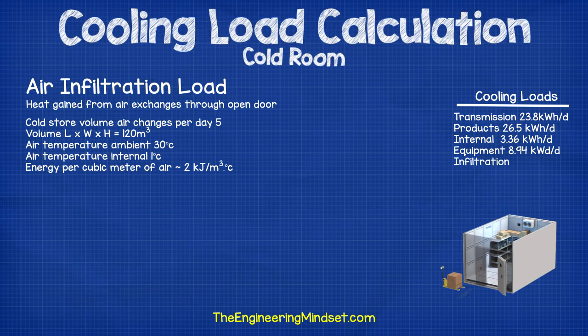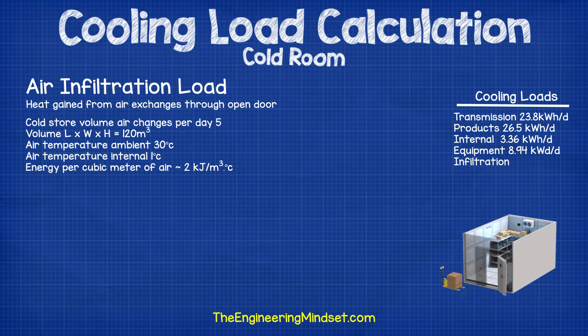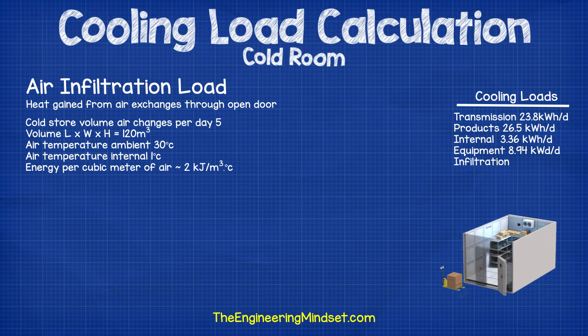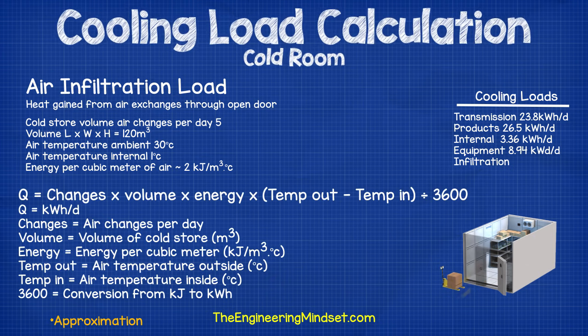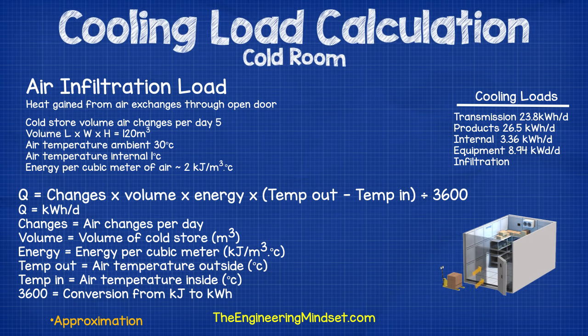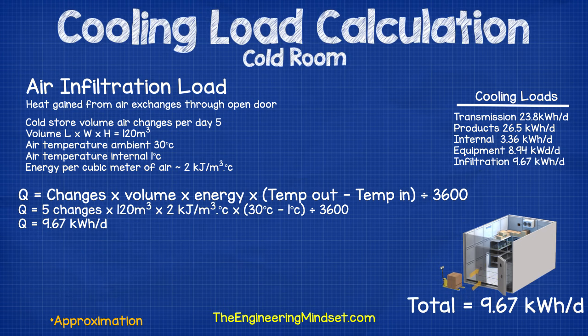Now we need to calculate the heat load from air infiltration. I'm using a simplified equation, but depending on how critical your calculation is you may need more comprehensive formulas for greater precision. We'll estimate five volume air changes per day due to the door being open, with a cold store volume of 120 cubic meters. Each cubic meter of air provides around 2 kilojoules of heat per degree Celsius of temperature difference, with outside air at 30°C and inside air at 1°C. Using the formula q equals changes multiplied by volume multiplied by energy multiplied by (temp out minus temp in) divided by 3600, this comes out to 9.67 kilowatt hours per day.